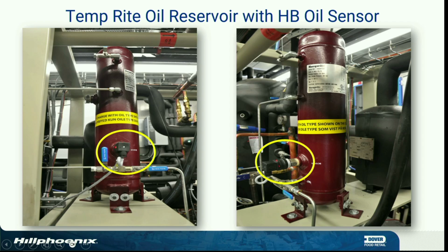Now, if you're on a job site at 2 o'clock in the morning and his separator sensor's bad, he's not screwed. He can just take the one off the reservoir, take the head off, plug it on that one, take that alarm, change it into a notice, and you're good to go. Order another sensor, get it out, replace the one on your reservoir. All right? Save that well, because you can use that for testing sensors in the future.